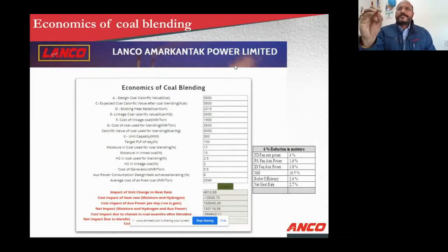So you can see just one small example of how the aux power will be impacted due to the moisture also. Aux power impacts the heat rate, that is given by the OEM, but by experiment or certain thumb rule, like if 6% reduction in the moisture will impact FD fan aux power by 4%, PA fan aux power by 1.6%, ID fan 3.8%, mill 16%. So like that, and whereas heat rate and boiler efficiency, that relationship is always given. So these things are put into the formulas, and we have tried to convert it into cost just for making the decision-making process more effective.